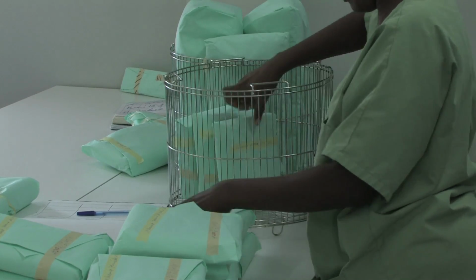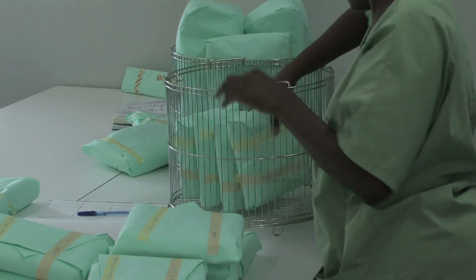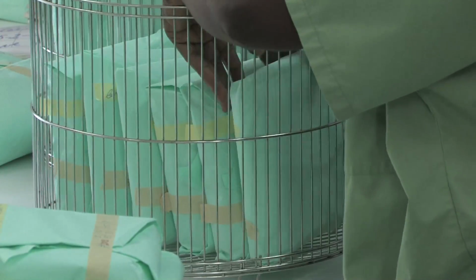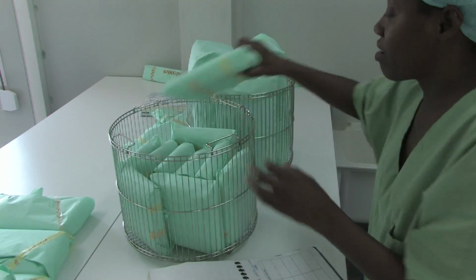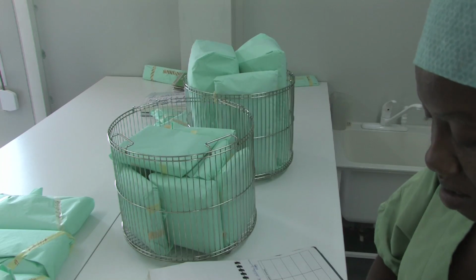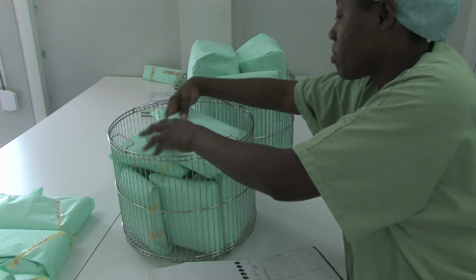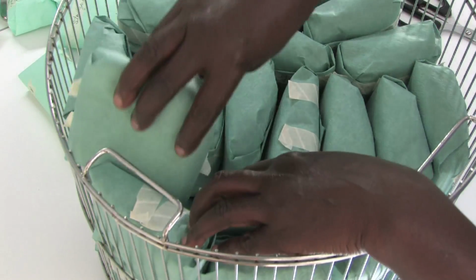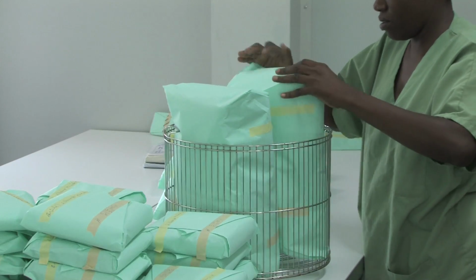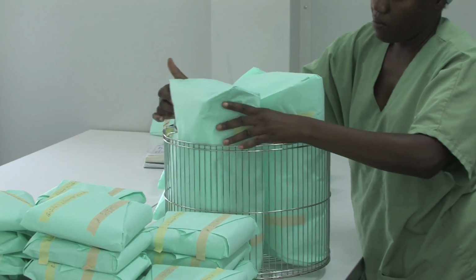3. Place the items to be sterilized in the baskets. Be sure to leave enough room between packs for steam to circulate freely. Do not overfill the lower basket, because if the upper basket rests on the packs, the paper may be perforated. The bulkiest packs should always be placed in the upper basket.